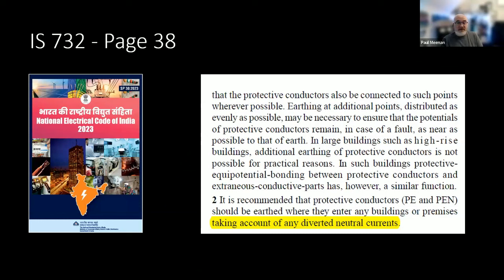Just worth noting, on Indian Standard 732, page 38, it actually mentions diverted neutral current three times. So it's quite interesting where protective earth or PEN conductors should be earthed where they enter any buildings or premises. Configuration is key. You may want to think, what do I bond? Where do I bond? How do I earth it? Do I introduce a greater level of diverted currents?